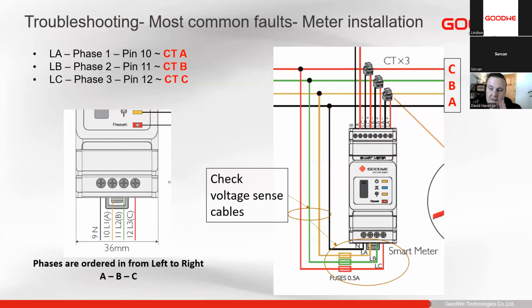So typically if our CT is the wrong way around, we'll see the right amount of current flowing, the right amount of power flowing, but in the wrong direction. But if our voltage sense is incorrect, we'll see the wrong direction as well as an incorrect amount of power going through the CT. So it's very important to make sure that our voltage sense is correct.